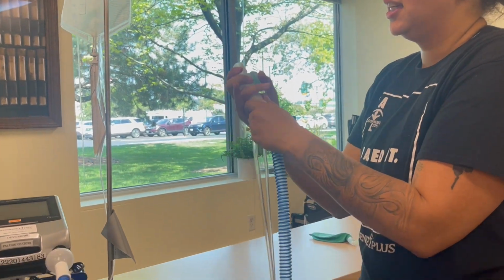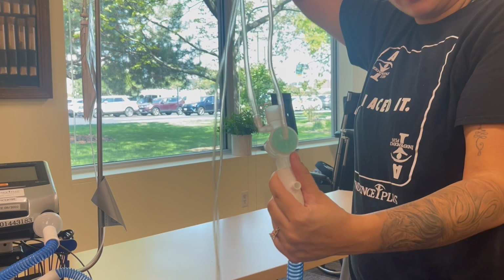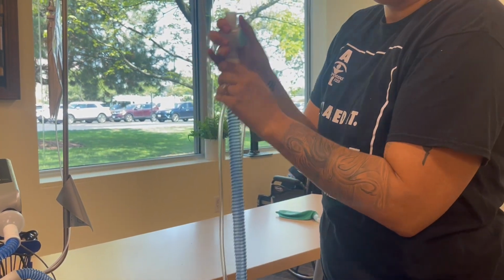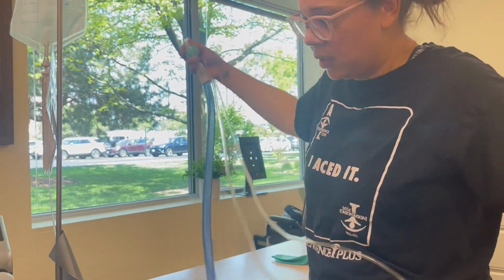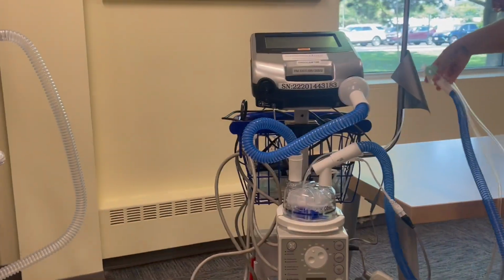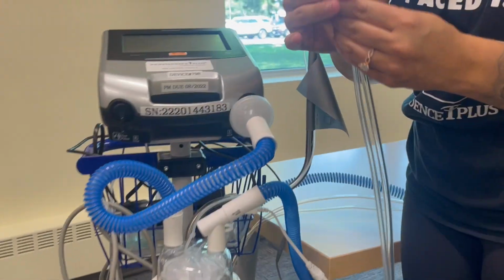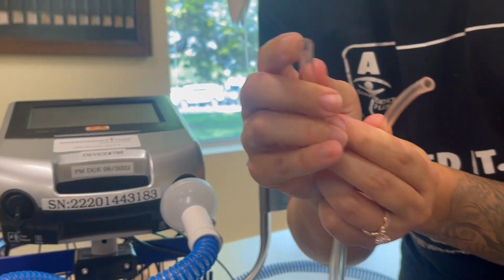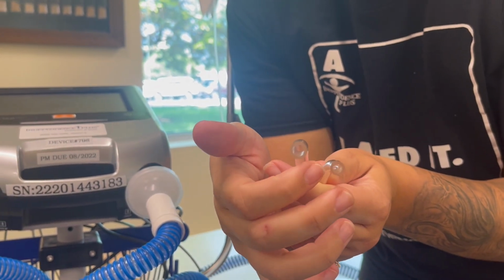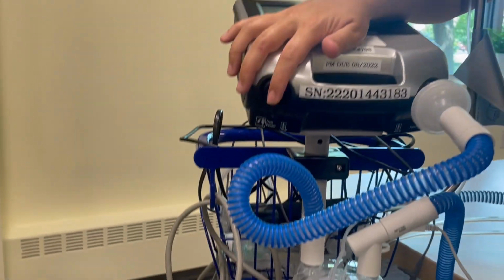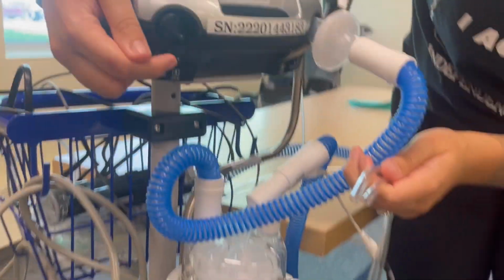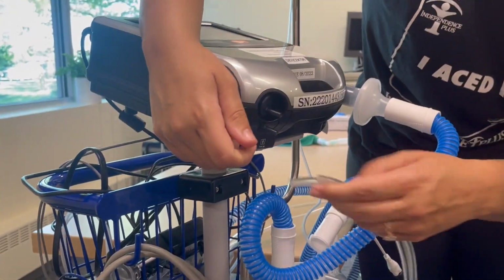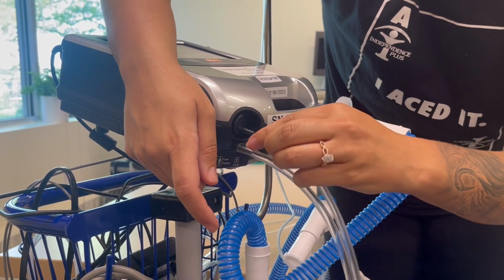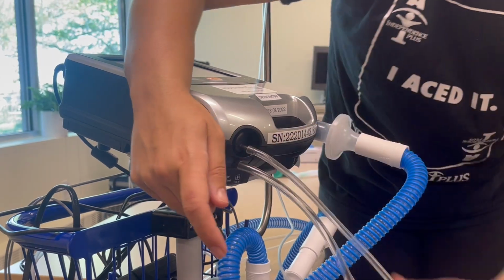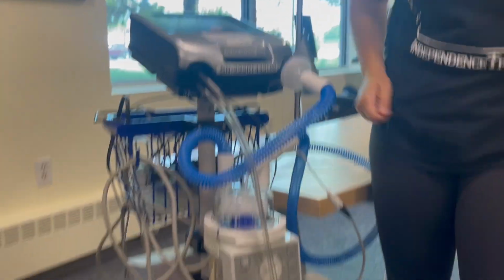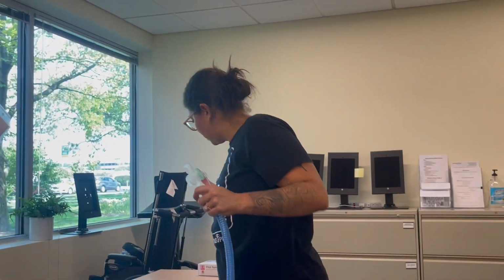You do have to be careful because it can connect either way, but if I connect it this way, my wires are gonna be running up by the patient. So I wanna make sure they're connecting down so that I can now plug them in to my astral vent. Here, this is really hard to see, but one of these tubes is a little bit bigger than the other one. So this one's a little bigger than this one, and one of these nozzles is a little bit bigger than the other one, and it's the bottom that's bigger than the top. So they do actually only fit one way. So on the bottom, I'll connect one on the top, I'll connect the other, and that way I know they're where they're supposed to go. So now I can connect my dead space.